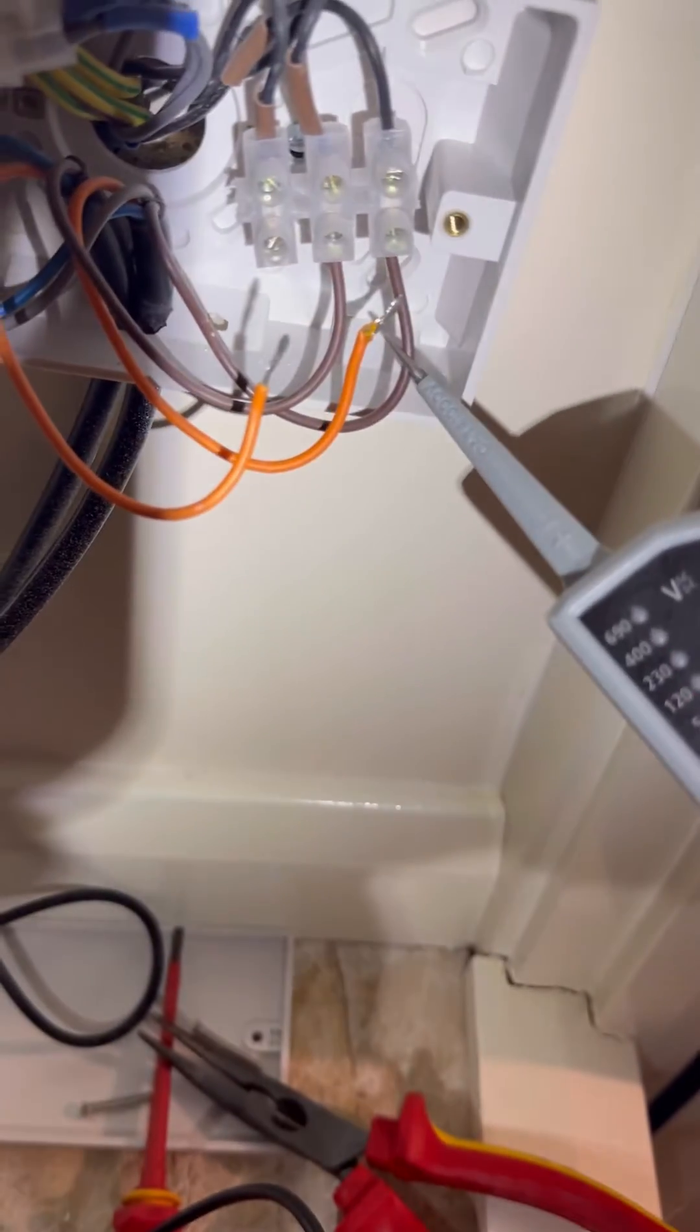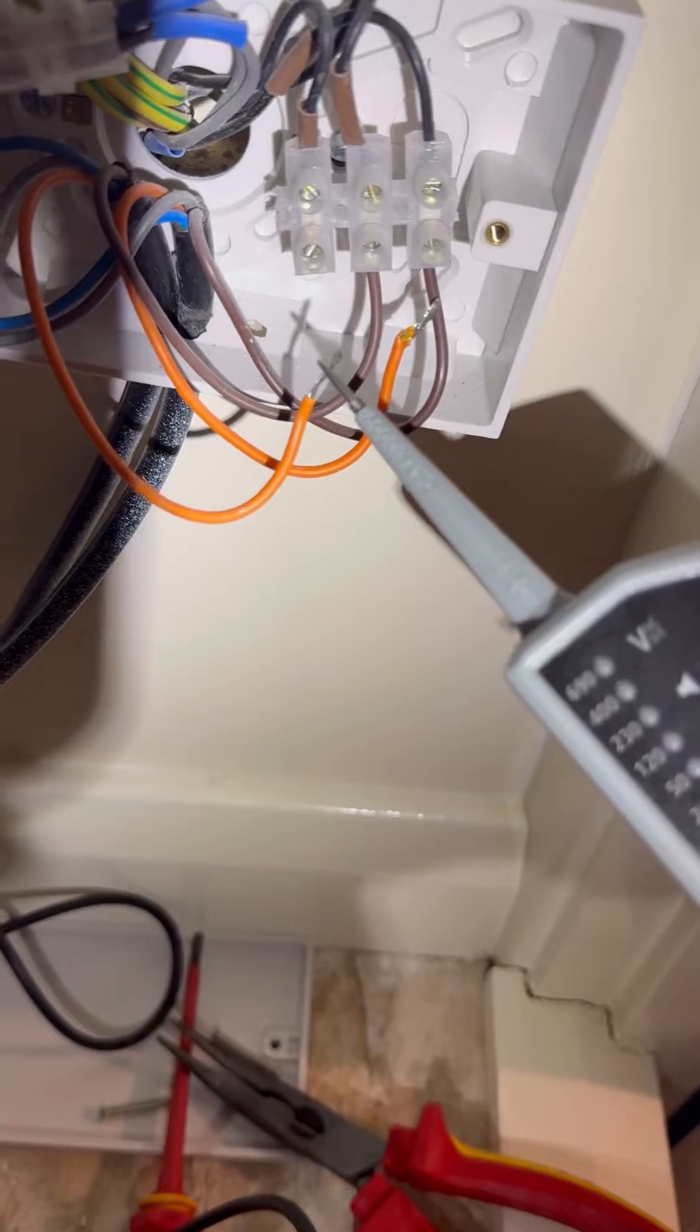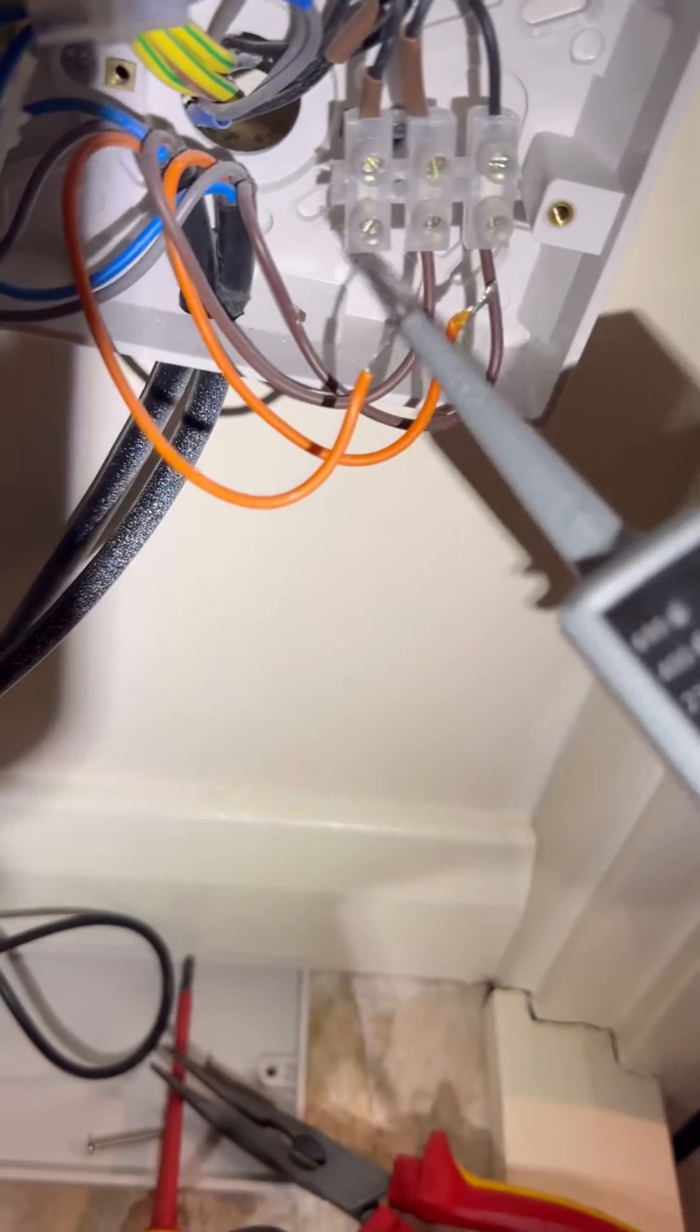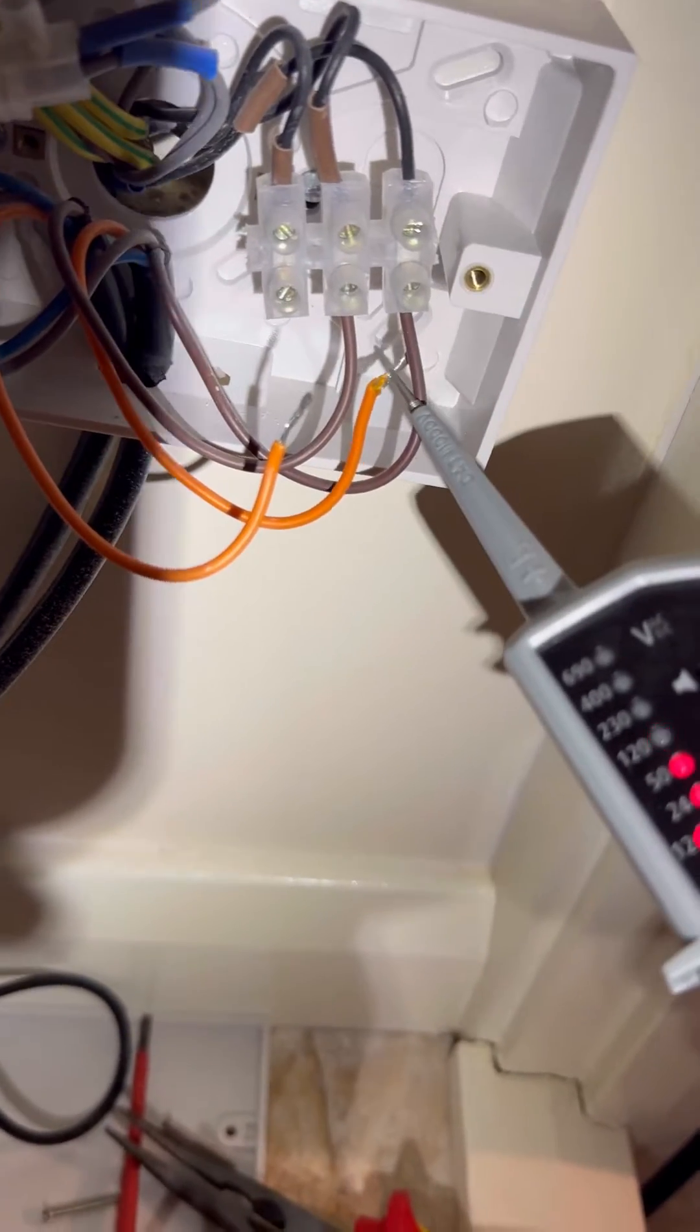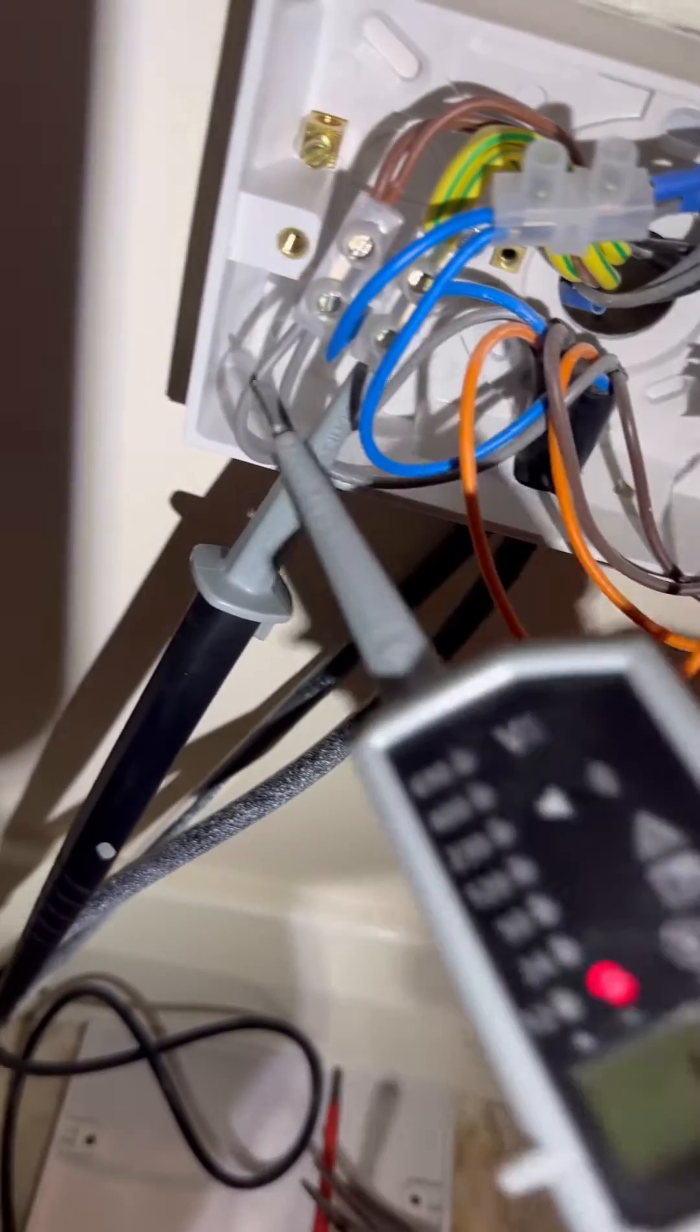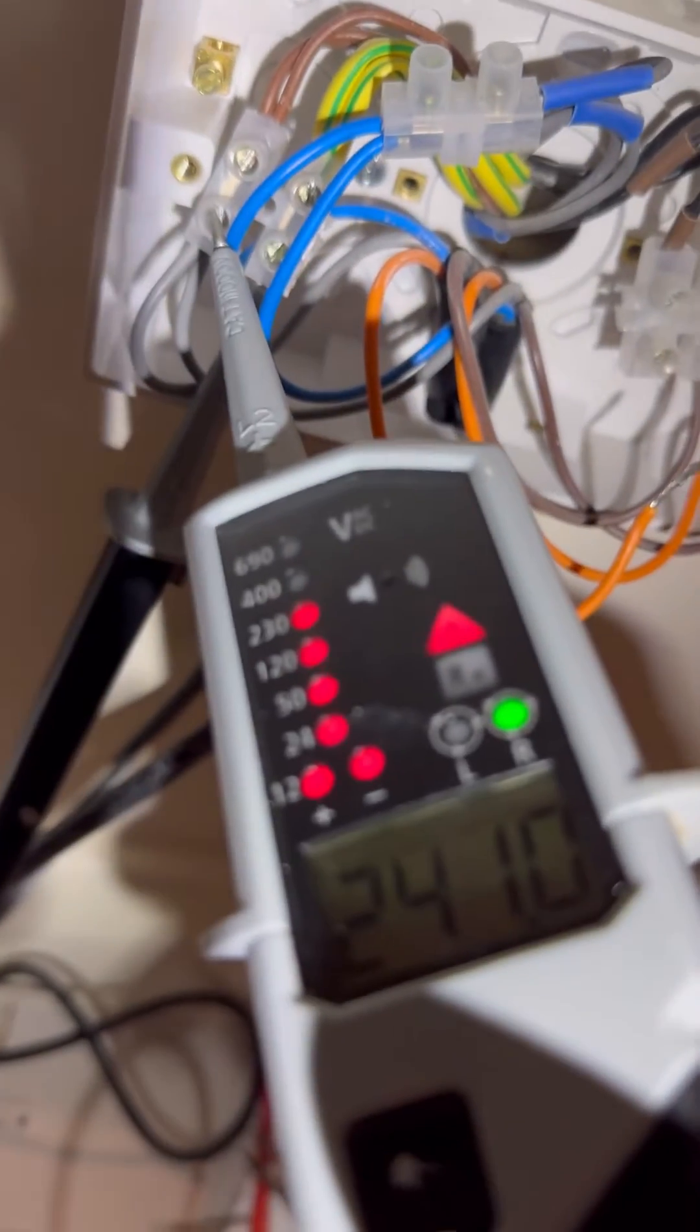So it's coming from the valve. So what's happening is the gray is obviously stuck, sending power through to orange, and then that's what's keeping the boiler on. So the customer originally called me there for a faulty room stat, but we've just proved now that it's a faulty valve instead.